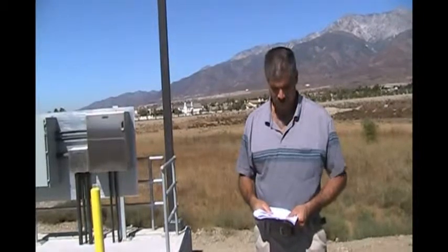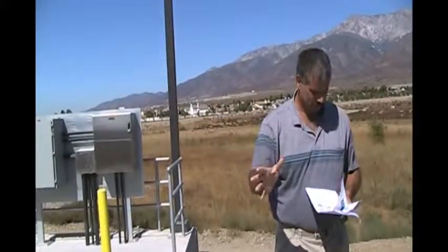When you guys are ready to put on 4, we'd be more than happy to get everything all dialed in and set up, and a lot of that groundwork's in place to make it easier since we already had that on the others. On this screen, basically, we have the level alarms. We talked about the lows and the highs. We have intrusion alarms, our wireless fault, and our communication fault. The wireless has to do with communicating to basin 5, and the communications back to SCADA. Those are about the only things that really can pop up on this particular thing. We don't have any power monitoring on this because when the power goes out, there's nothing left. So, any questions on this one?